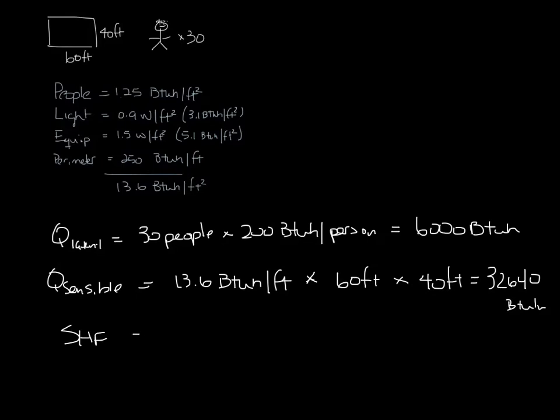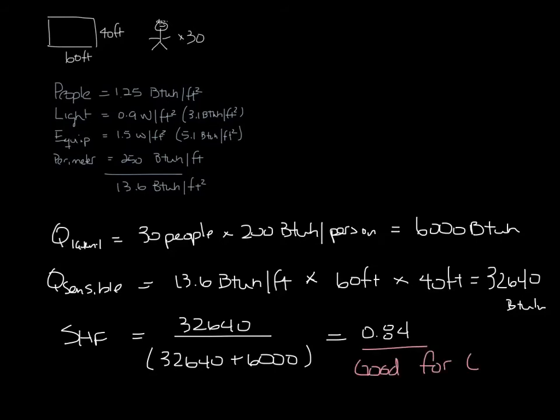Now we can calculate the sensible heat factor, which is 32,640 sensible load divided by the total load, which is 6,000 plus 32,640, and that equals 0.84, which makes it good for a chilled beam application.